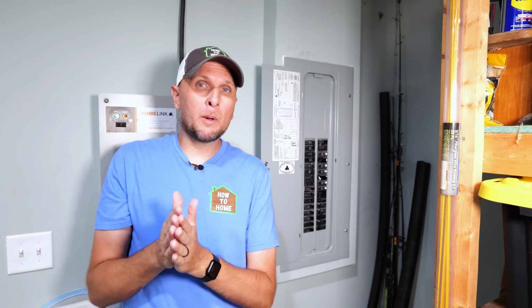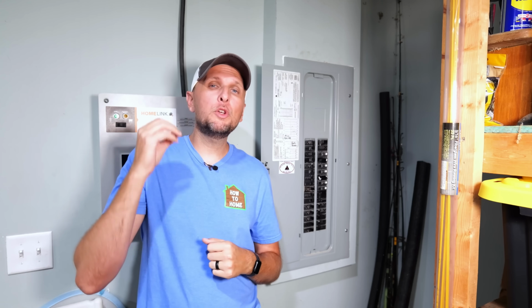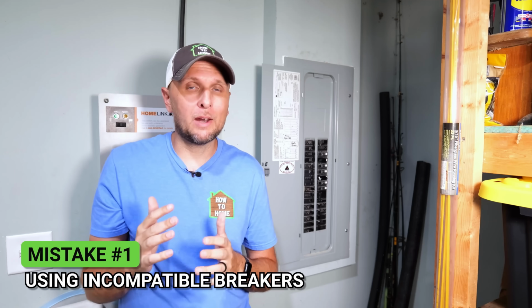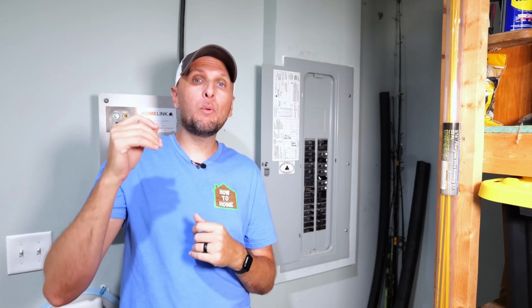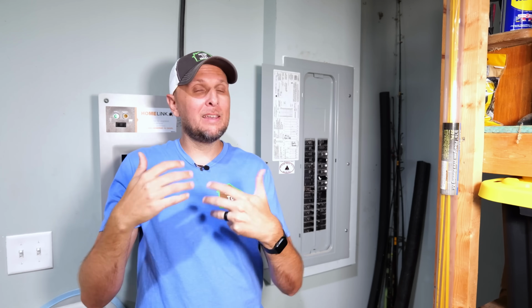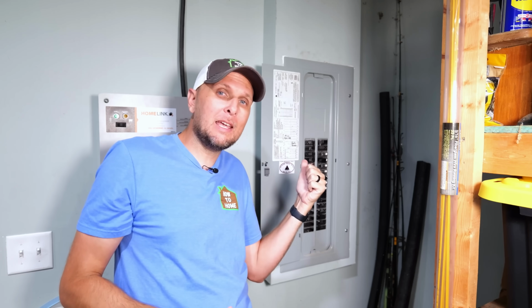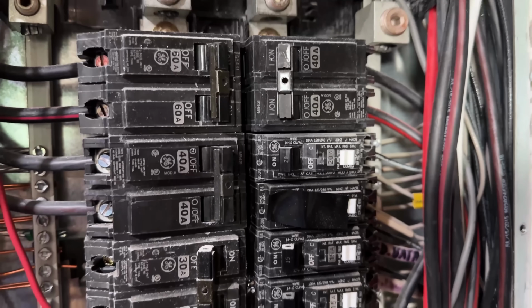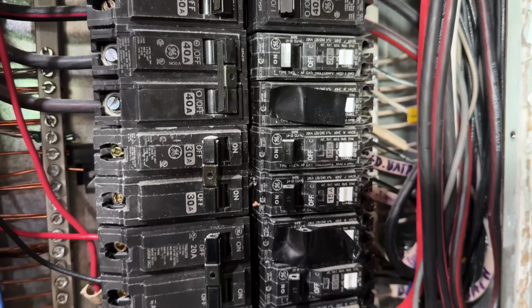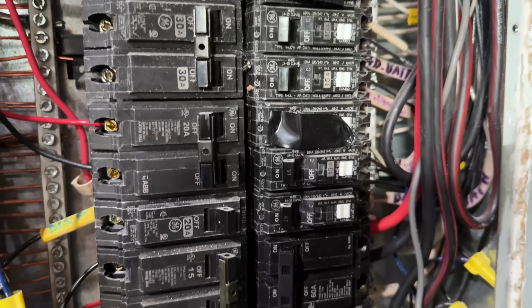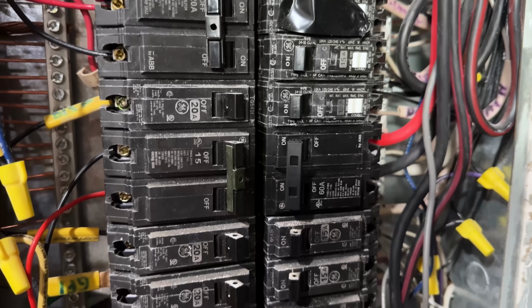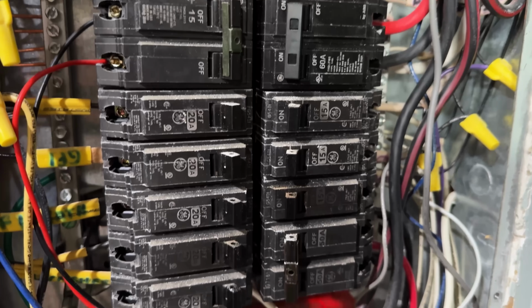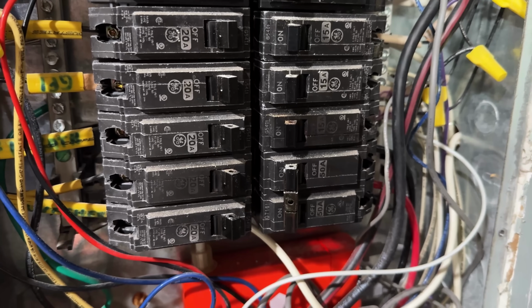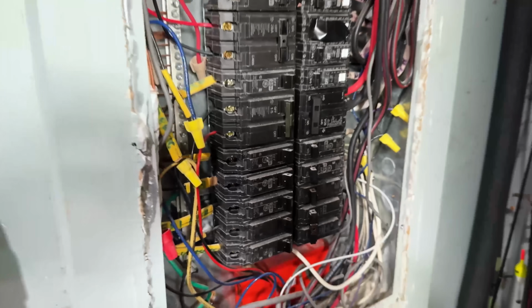First up on our list of big mistakes is using breakers that don't match your panel. I've seen people put a Square D breaker in an Eaton panel, for instance. This is a GE panel, but just for example purposes, they'll take a Square D breaker and put it in an Eaton panel just because it can physically fit in there, and that can cause a huge problem. Just because it snaps in doesn't mean it's actually safe. Those breakers haven't been tested together, so they might not trip properly during a fault, which can lead to very dangerous situations.